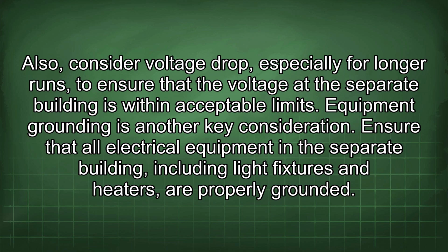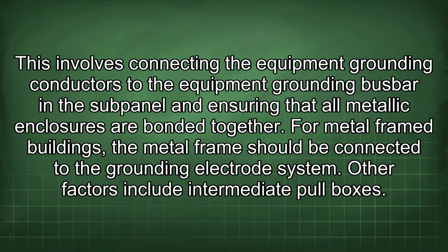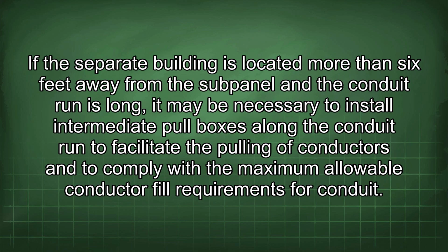Ensure that all electrical equipment in the separate building, including light fixtures and heaters, are properly grounded. This involves connecting the equipment grounding conductors to the equipment grounding busbar in the subpanel and ensuring that all metallic enclosures are bonded together. For metal-framed buildings, the metal frame should be connected to the grounding electrode system. Other factors include intermediate pull boxes. If the separate building is located more than 6 feet away from the subpanel and the conduit run is long, it may be necessary to install intermediate pull boxes along the conduit run to facilitate the pulling of conductors and to comply with the maximum allowable conductor fill requirements for conduit.